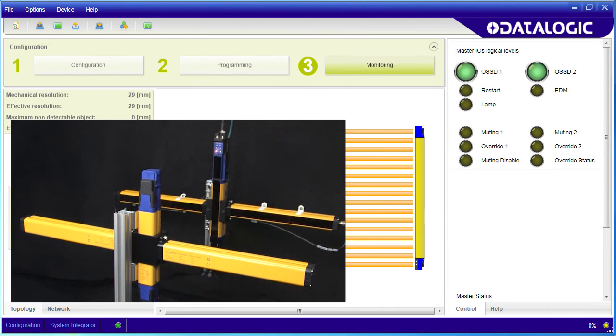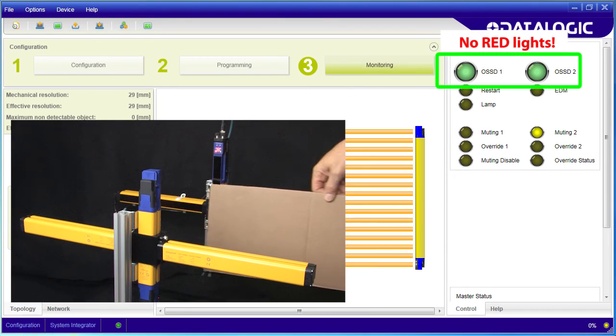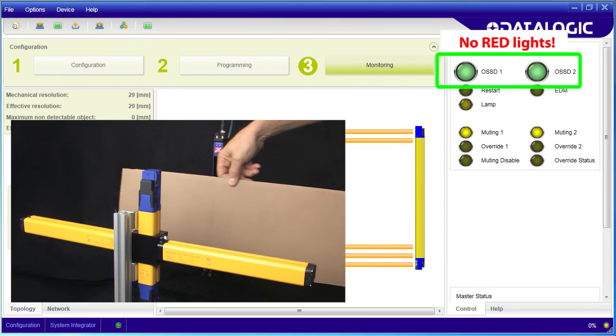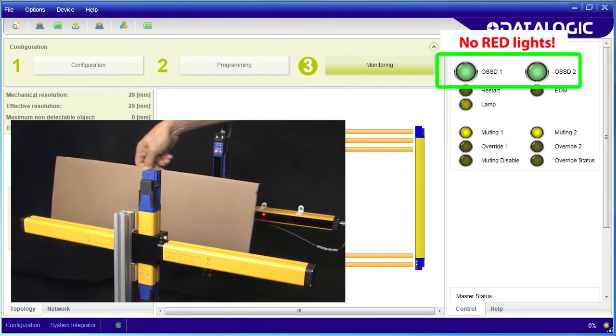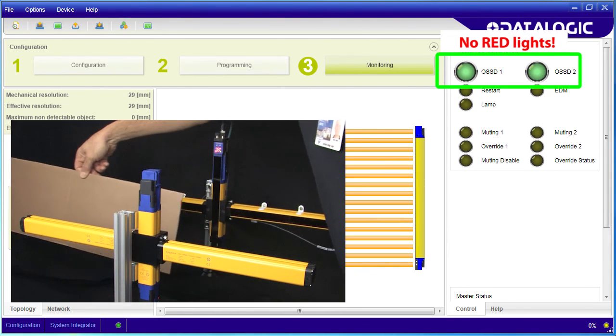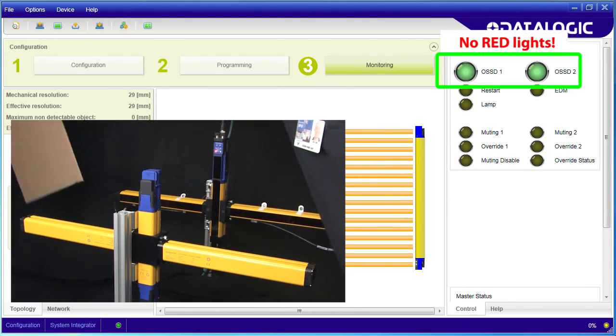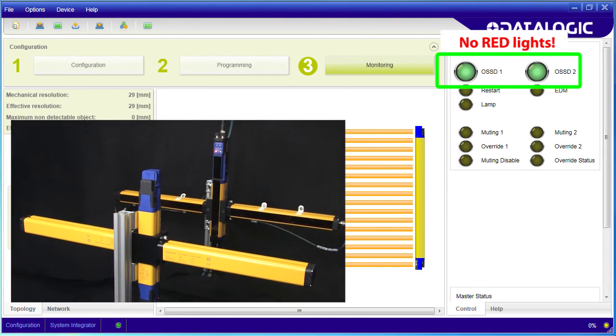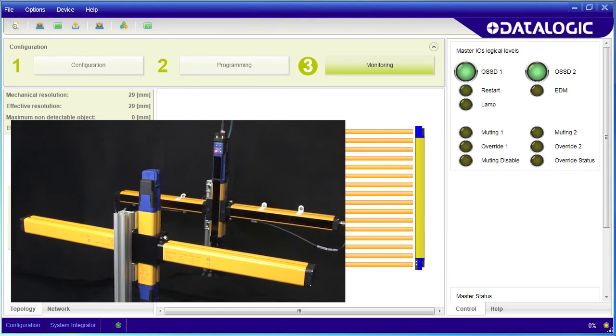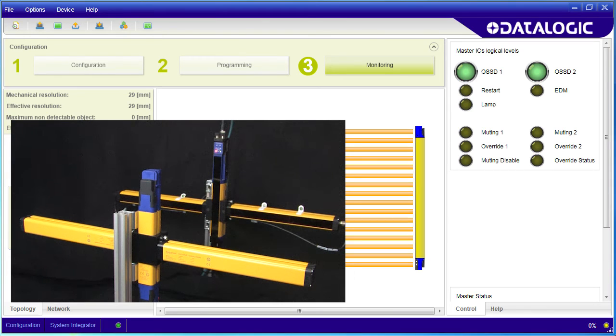But if I have a large pallet of stuff moving into the area that is longer than this distance, it passes through the light curtains without tripping the output signals. Exactly what we expect. Perfect. The light curtain saw the large object coming and muted itself so it could pass.